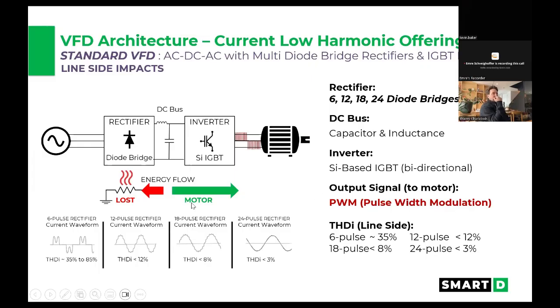How do we get around that? Well, some people are not looking to rectify anything on the line side, so they just leave it as a 6-pulse rectifier, a standard VFD, a naked VFD, if you will, and your harmonic distortion is going to be 35 to 85%. Then you can also make it a 12-pulse rectifier, where you multiply the number of diodes and you end up with 12 instead of 6, and your total distortion is a little bit better. You're at about 12%. And as you continue to increase your diodes on your front end, you can get that distortion down to 8 and then finally to 3 with a 24-pulse rectifier, which is kind of rare.